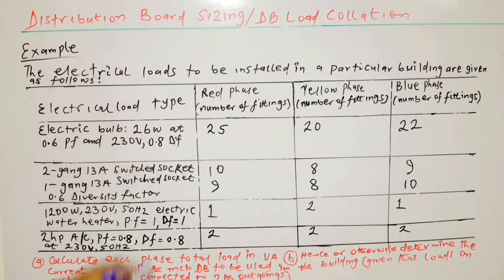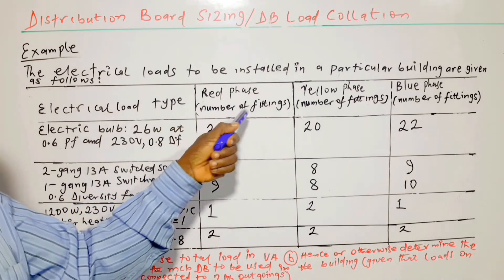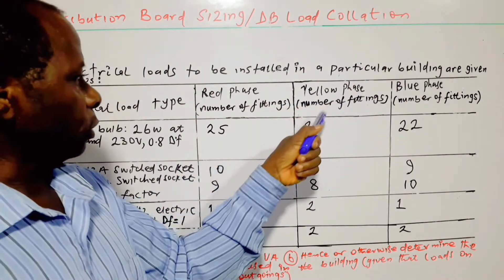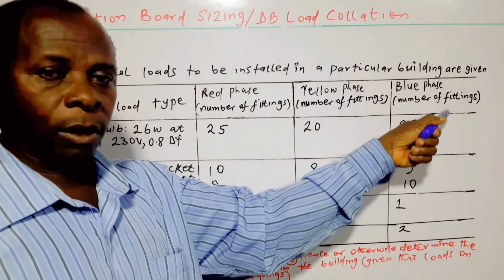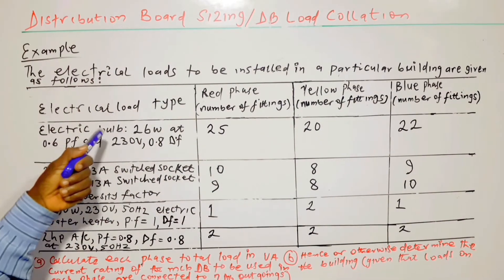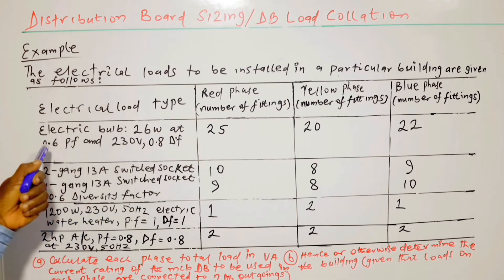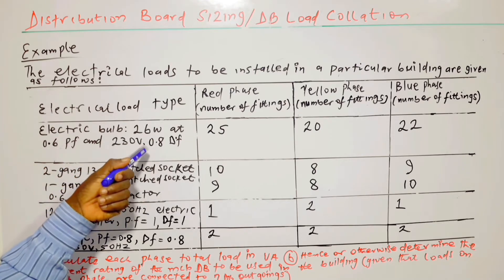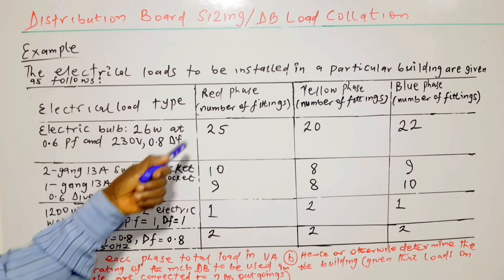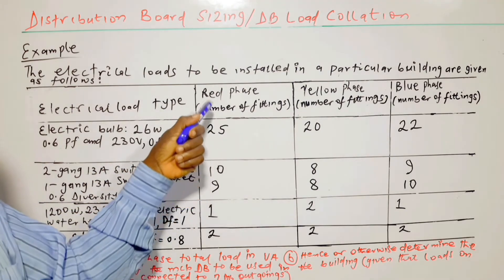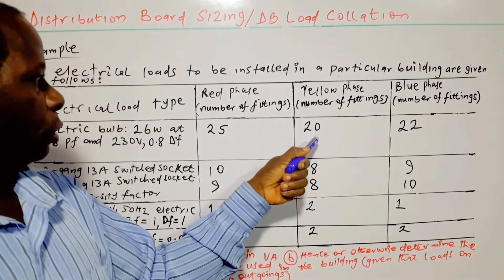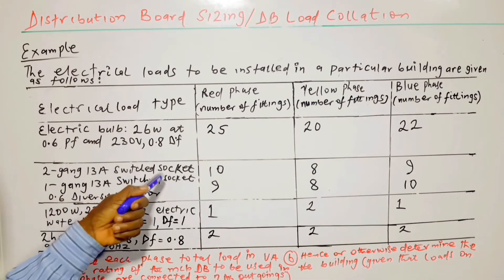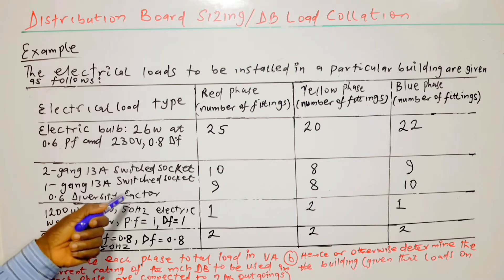The electrical load types are listed with the number of fittings or appliances on each phase — red, yellow, and blue. For electrical bulbs rated at 26 watts, 0.6 power factor, 230 volts, and 0.8 diversity factor: we have 25 on the red phase, 20 on the yellow phase, and 22 on the blue phase.